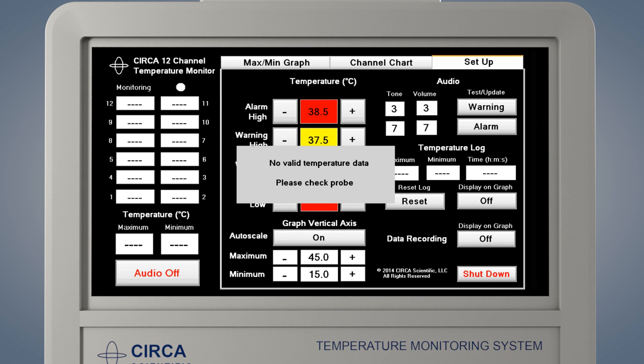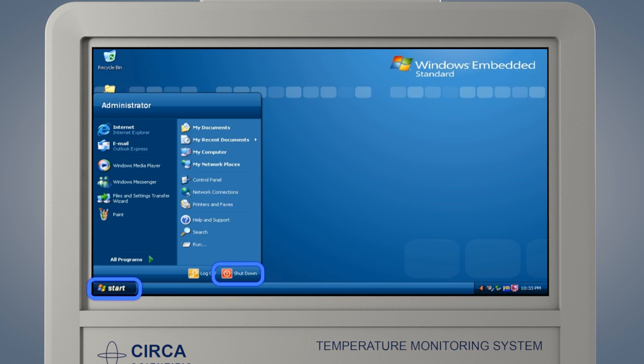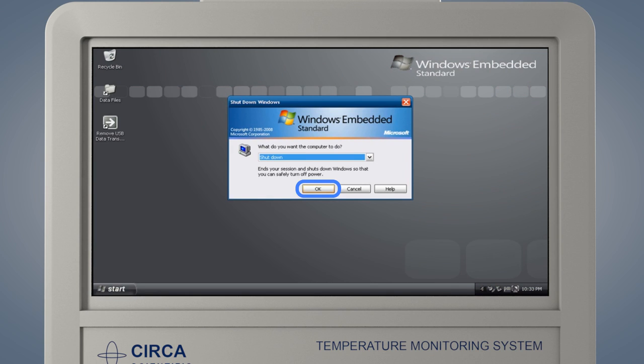The power button on the back of the monitor should never be used to shut down the monitor. To properly shut down the CIRCA monitor, go to the Setup screen. From the Setup page, press Shut Down. This will close the CIRCA software and return the user to the monitor home screen. Touch the Start button and then press Shut Down. Touch OK to complete the shutdown process.